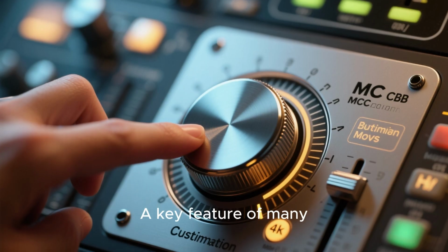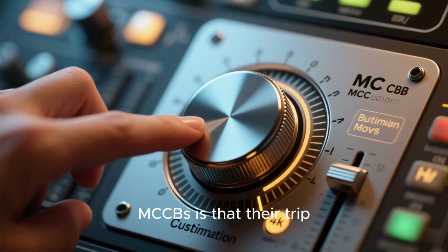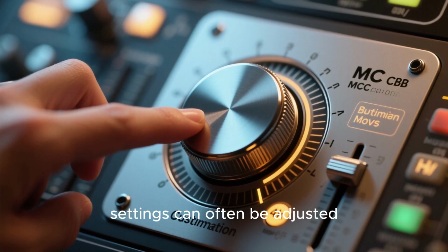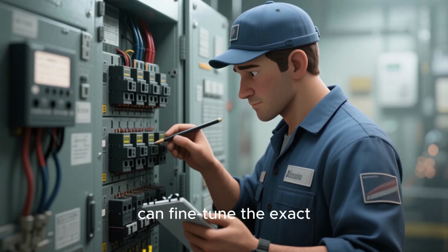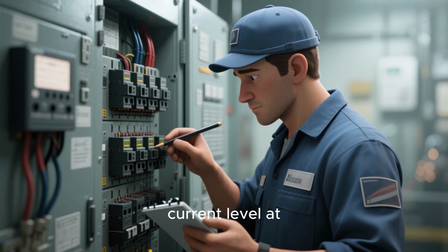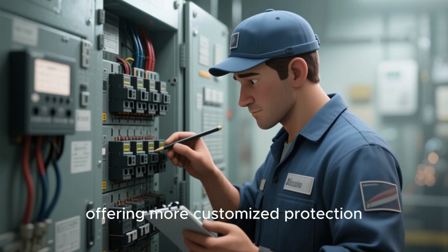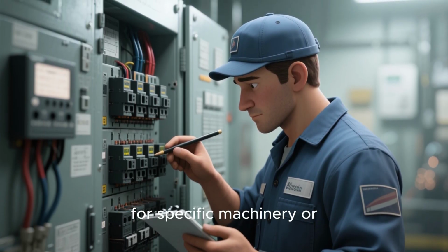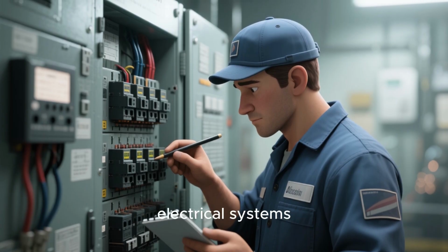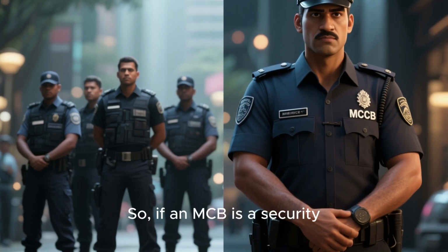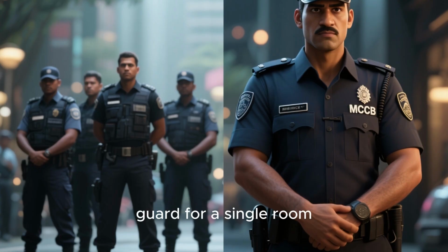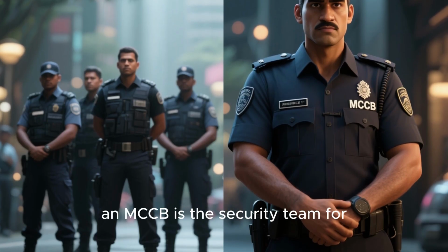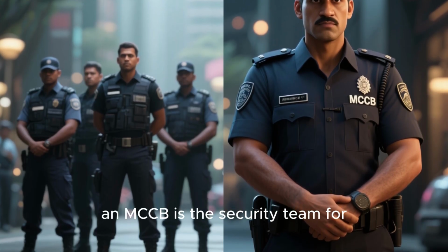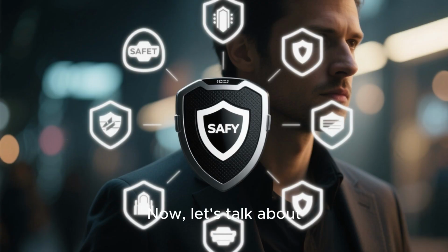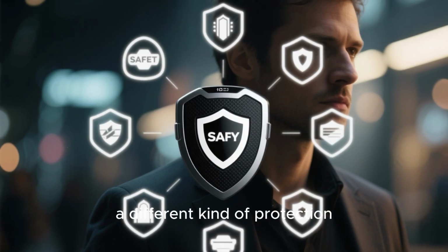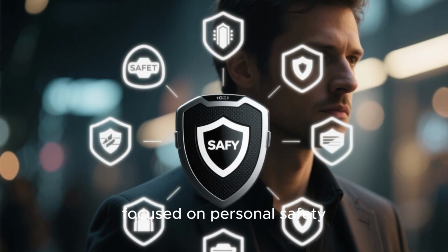A key feature of many MCCBs is that their trip settings can often be adjusted. This means an electrician can fine-tune the exact current level at which the breaker will trip, offering more customized protection for specific machinery or electrical systems. So, if an MCB is a security guard for a single room, an MCCB is the security team for the entire building. Now, let's talk about a different kind of protection focused on personal safety.